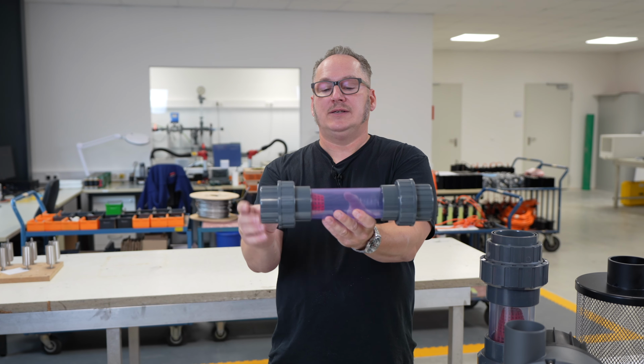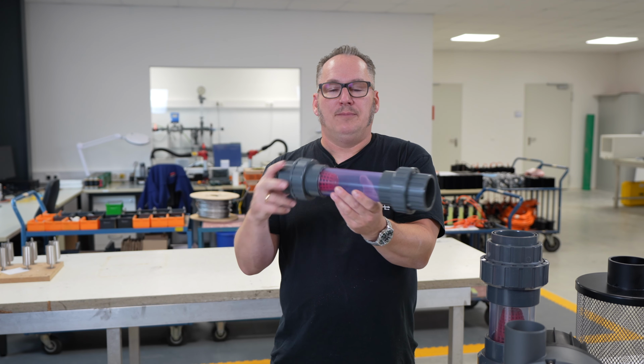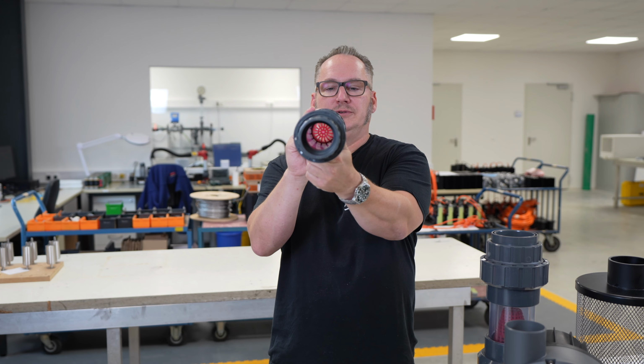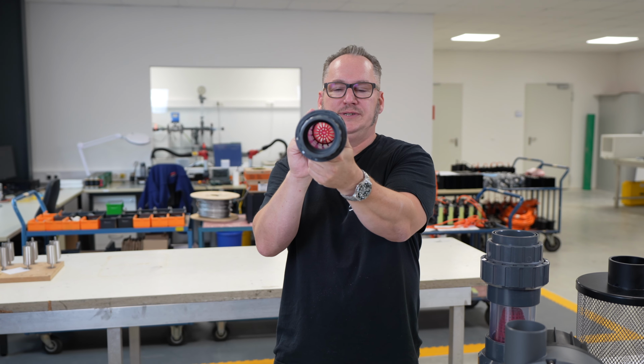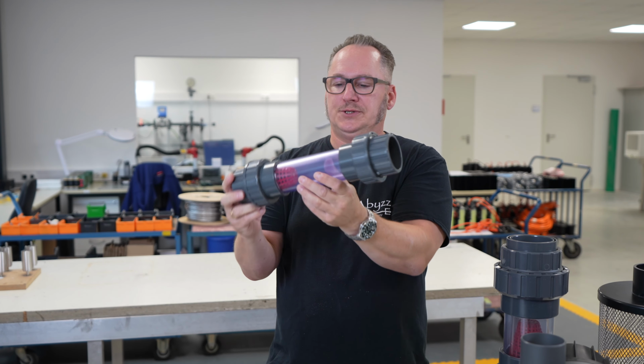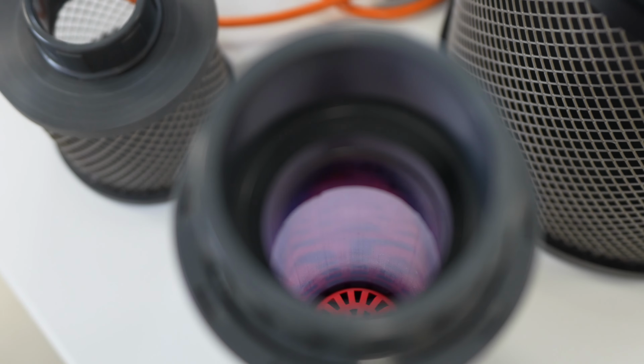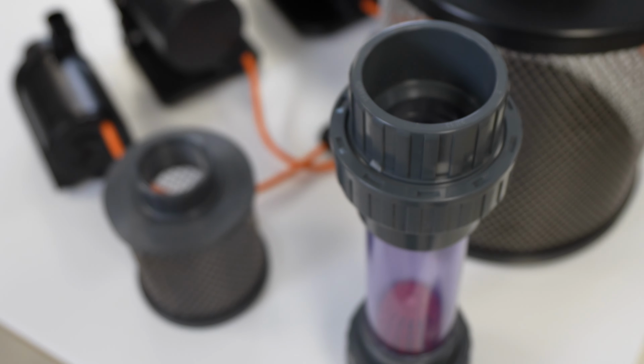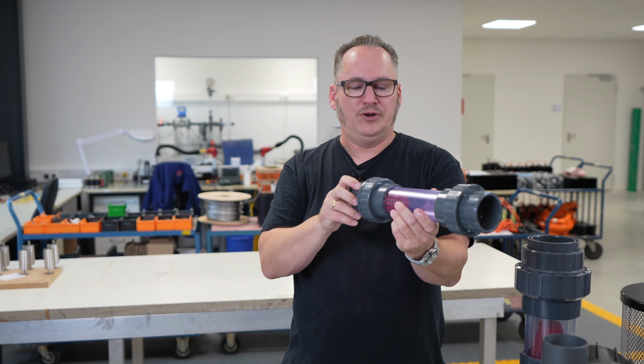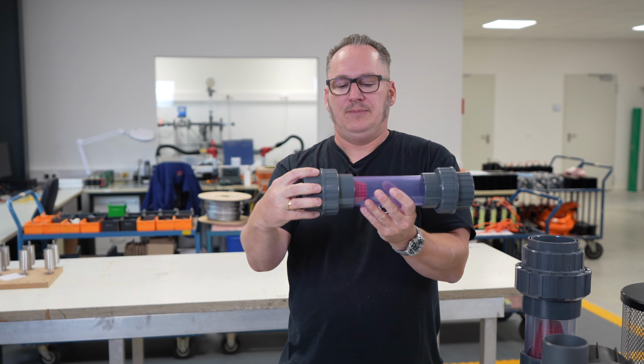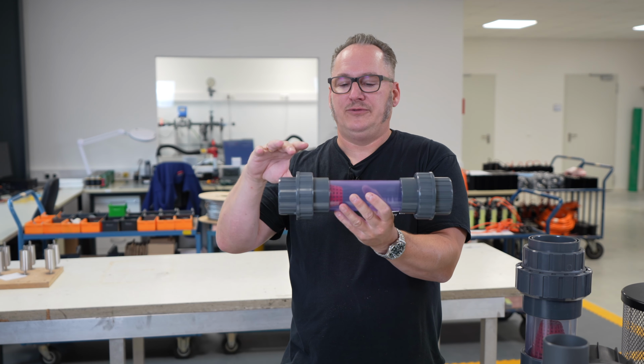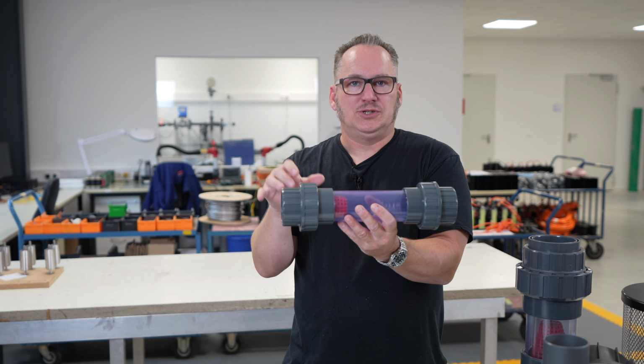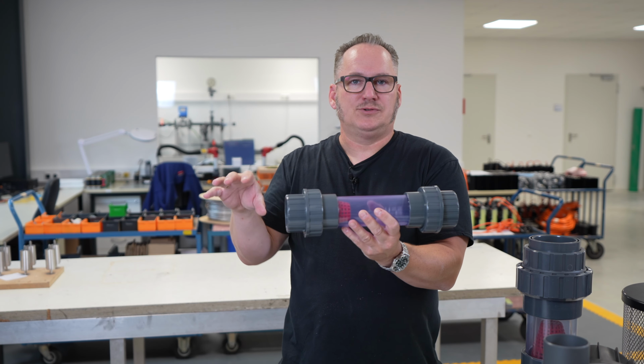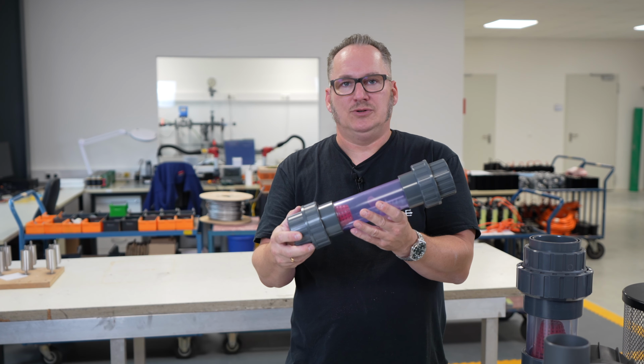Those strainers look as if they don't let a lot of water through, but if you look closely from the front, you'll see that it almost has no resistance against that inrushing water. It also makes sure that you have a long run straight in front of your pump. So don't make the mistake of putting a 90-degree elbow right in front of it, but use this. The pump connects directly to here, and then you have your 5 times DN, which is the minimum distance the water should travel straight to have an ideal situation on your impeller wheel.